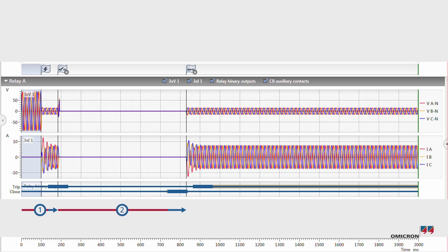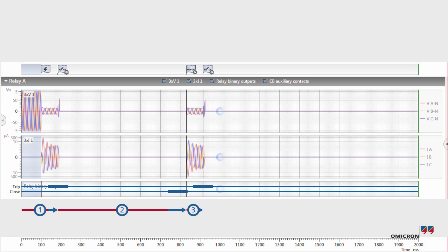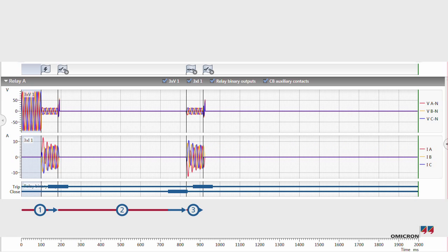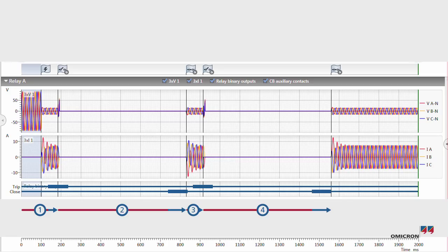As expected, the relay trips a second time. RelaySimtest then correctly simulates the circuit breaker opening for the second time. The relay attempts to reclose for a second time, and RelaySimtest responds correctly with an iteration that puts the fault current back on again.